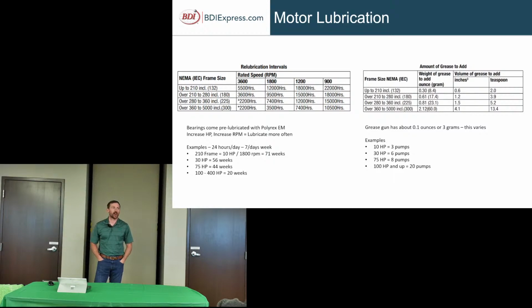So motor lubrication, how often are you guys lubricating your motors? Once a year. So motor lubrication, when you're lubricating the bearings that are in there, these lubrication intervals are going to be much larger depending on the horsepower size. The higher up you go on your horsepower, you're going to be lubricating it less periodically, but also speed is a factor of that. And on this chart here, it's also going to vary on your frame size. Frame size is going to tell us what bearings are in there. And then on my next slide after this, I'll talk about the procedures to doing that.